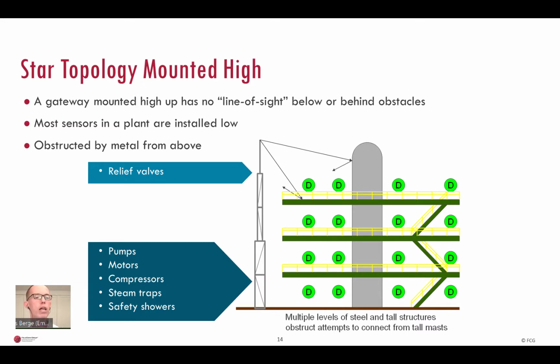Therefore, they are obstructed by multiple stories of metal also from above. So even a gateway mounted high up on a mast cannot connect to the ground level sensors or sensors behind a tall furnace or a column. Moreover, with the antenna in an elevated location, lightning-related risks increase. Sure, some sensors are installed high, but you can't have one wireless sensor network for those and another technology for all other sensors. You want a single network for all wireless sensors, so be careful.